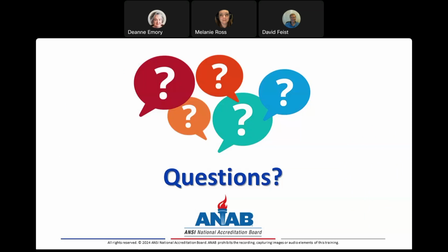Deanne, the first question that came in, is there a difference in the terms validation and verification? Yes, there are. Verification is the provision of objective evidence that a given item fulfills specified requirements. So verification points back to requirements. So can your lab meet the requirements of the method that you are choosing? Validation is a verification where the specified requirements are adequate for intended use. Validation points forward to the user. Is this the proper method for the intended use?